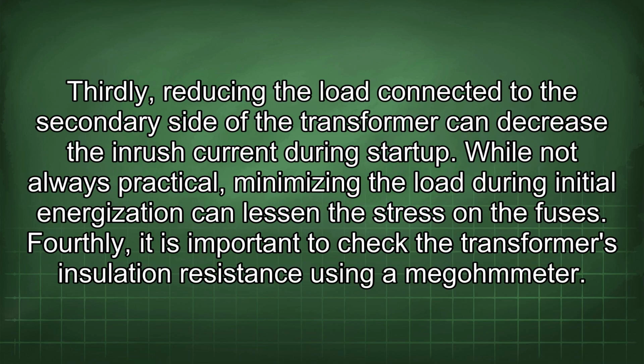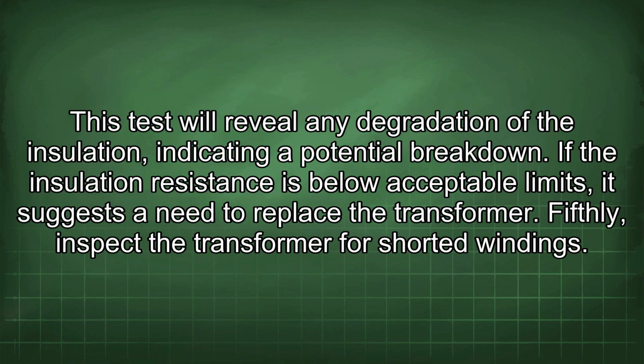Thirdly, reducing the load connected to the secondary side of the transformer can decrease the inrush current during startup. While not always practical, minimizing the load during initial energization can lessen the stress on the fuses. Fourthly, it is important to check the transformer's insulation resistance using a megohmmeter. This test will reveal any degradation of the insulation, indicating a potential breakdown. If the insulation resistance is below acceptable limits, it suggests a need to replace the transformer.